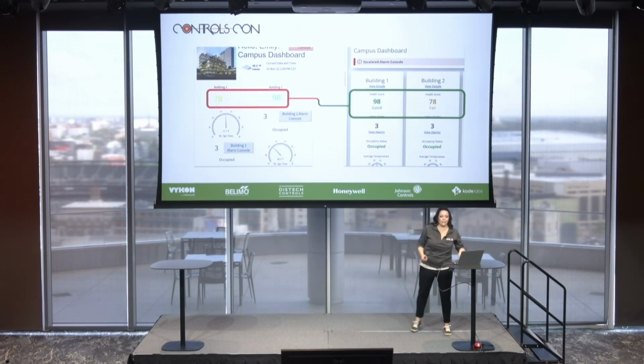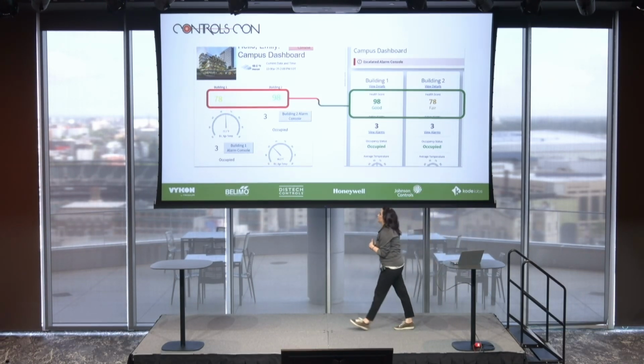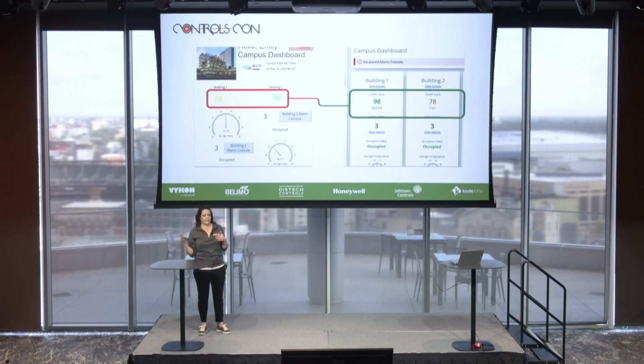And accessibility. So accessibility is not just about color, because on the left side, I would not know that yellow is actually not good. So you want to make sure you have both labels and colors that are in contrast when you're using color, because with accessibility standards, color cannot denote a status without having a secondary way of knowing what that status is. So anytime you're using color as a status, you want to make sure that you've got a label or some way that you're also denoting what that status is.